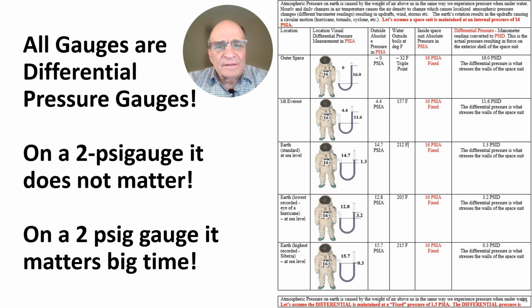To get a better understanding of this differential pressure, I'm using this graphic that's shown here. I have a person in a spacesuit, and he's in outer space. The absolute pressure in outer space is 0. So the spacesuit experiences 16 psi, and the differential pressure between the pressure in the spacesuit and the outside environment is 16 psi differential pressure. Let's say the person in the spacesuit is still maintained at 16 psi absolute, and the person is on top of Mount Everest. At the top of Mount Everest, the pressure is only 4.4 psi absolute, so the differential pressure is 11.6 psi differential.